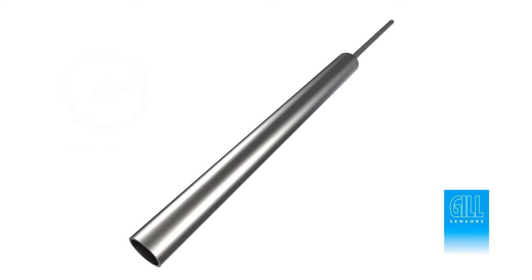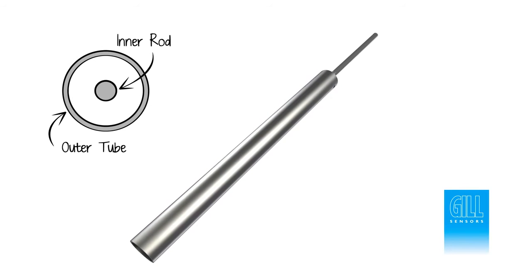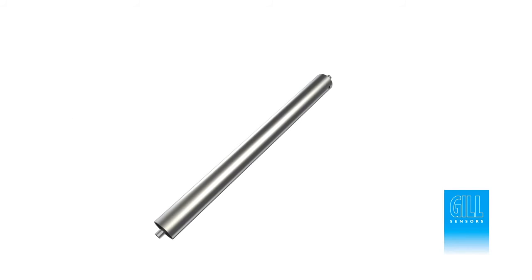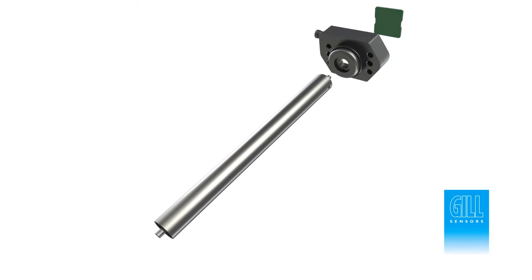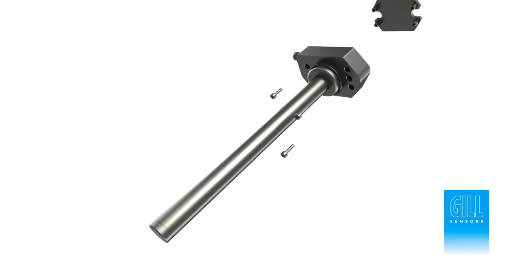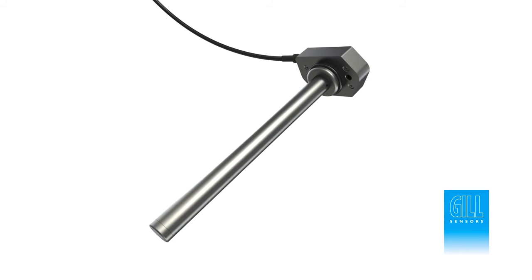Capacitor plates can also be deployed as concentric tubes, with the advantage of reduced interference, as well as improvements in mechanical stiffness and robustness. Fully integrated electronics mean no external electronic units are required, as all signal processing is managed on board. Dielectric fluctuation caused by temperature variation is managed using offset values also stored within the sensor memory. These values are typically applied during factory calibration at Gill Sensors.